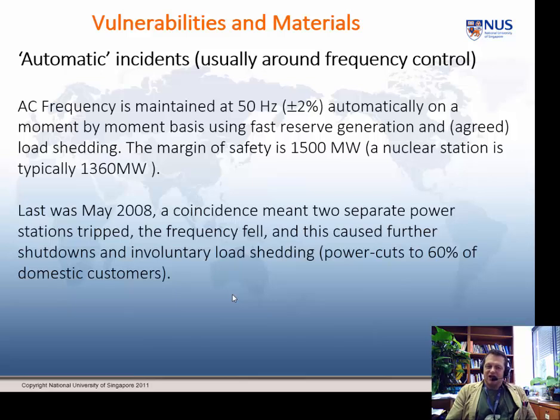As well as fast reserve, they have what's called plumbed-in load shedding or integrated load shedding. So what happens is, I'm a big company maybe and I have a very large energy demand. My electricity company will approach me and say, look, we'll give you a cheaper rate if you will let us wire your supply so that if we have, for instance, a frequency incident, which is what we're talking about now, we can just disconnect your supply, probably for a few seconds, and then put it back again just to keep the frequency above 48. And most industries can work with that because they have local capacity to buffer for a few minutes.